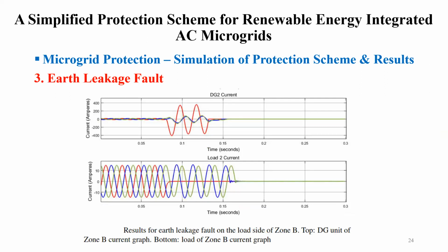Similarly, we also see the situation in case of an earth leakage fault. This is again the load side of the B distributed unit, and below is the current in the graph. In an earth leakage fault, the distributed unit is disconnected from the supply. Unless and until that ground fault is removed physically, the system should be disconnected from the supply, and that is what our protection scheme has done. The protection scheme has disconnected the distribution unit from the supply, and we can see that there is no further transmission of power.